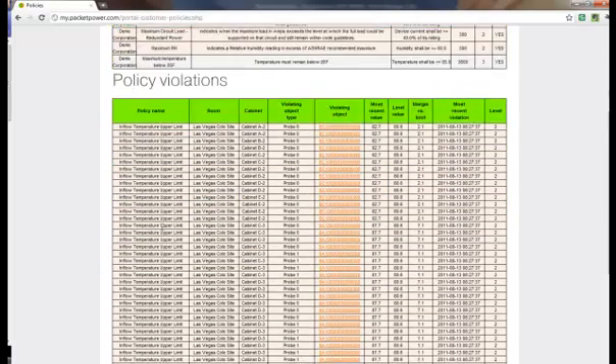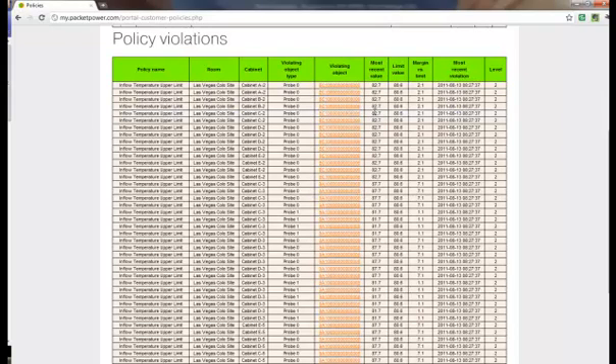In the policy violation area, you see the name of the policy, the location of the policy violation, the name of the monitoring device that reported the policy violation, the value of the reading of the monitoring device, the policy limit value, the difference to the limit value, and the date and time of the violation, as well as the level of severity that was assigned when the policy was defined.